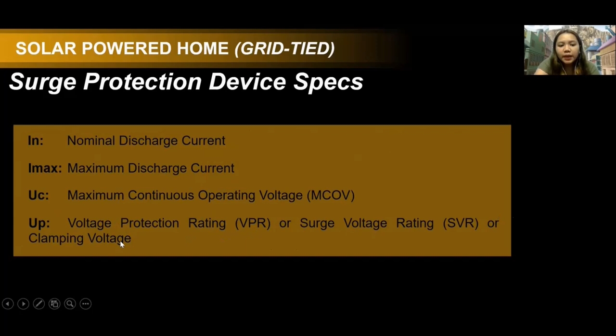By the way, the UC rating is the Maximum Continuous Operating Voltage or MCOV. Then there's IN, the Nominal Discharge Current; IMAX, the Maximum Discharge Current; and UP, the Voltage Protection Rating, also called Surge Voltage Rating or Clamping Voltage. Now let's go to the DC side.